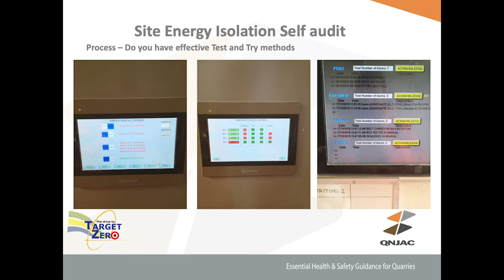So do your procedures include authorised persons ensuring equipment is safe to re-energise, and do you have formal procedures to ensure equipment has been returned to a safe condition before the isolation is removed? Are there robust handover procedures in place for shift changeover to ensure the isolation remains effective during handover? That's where we use the isolation certificates for that.